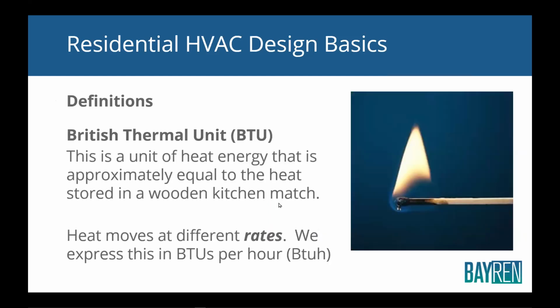So, what is a BTU? You hear us talk about BTUs all the time. If you take a wooden kitchen match and you strike that match and you let it burn all the way down till you have to let go of it, you've basically released about one BTU of heat into the air. So when we talk about a 40,000 BTU per hour furnace, what that means is it's putting about 40,000 kitchen matches worth of heat into that house in 1 hour. When we talk about a 36,000 BTU air conditioner, what that means is it's removing 36,000 kitchen matches worth of heat from the house in an hour. And so a house has a load in BTUs and equipment has capacity in BTUs. And the trick is matching those together, okay?